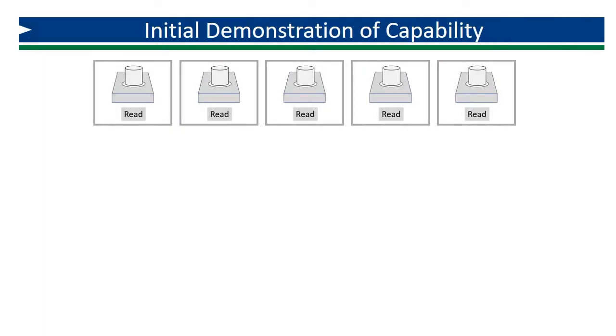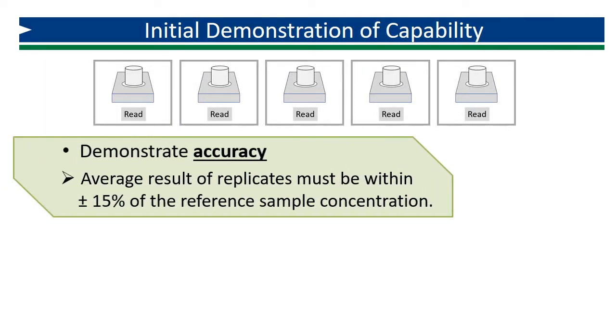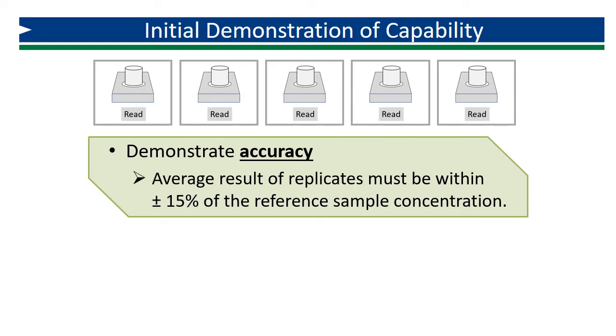When the five replicates have been analyzed, the analyst's accuracy is assessed by calculating the average result for comparison to the expected value. The average result must be within plus or minus 15% of the reference sample concentration.